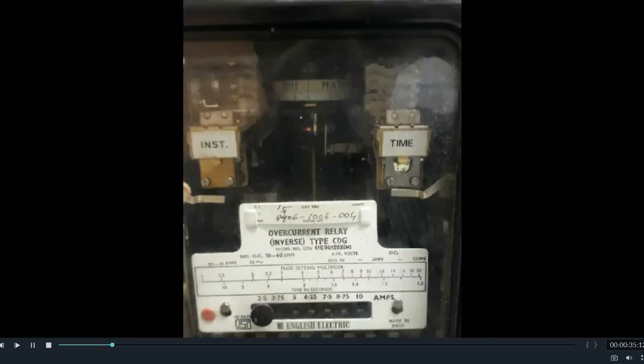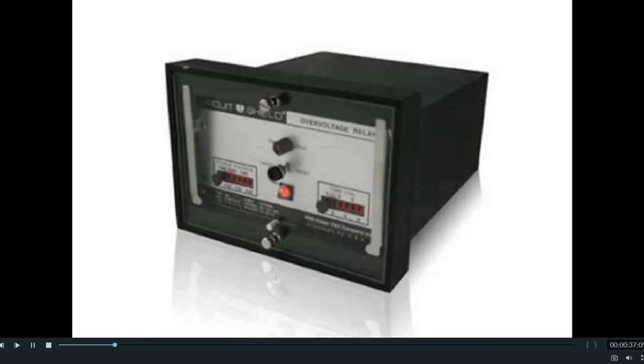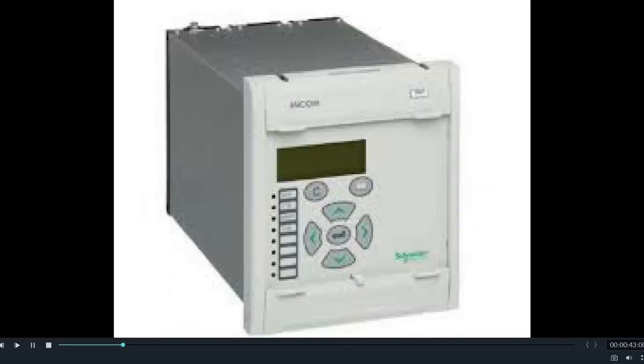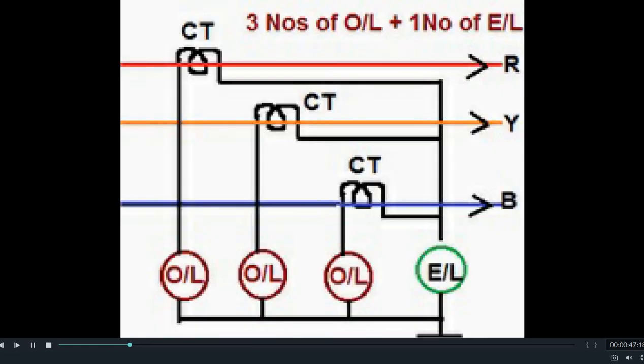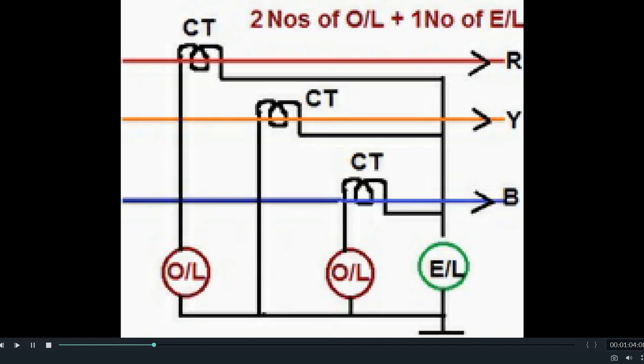These relays are available in all types — electromechanical, static relays, and numerical relays. Overcurrent and earth fault relays are generally used in groups. For any transmission line, there are always three overcurrent relays for three phases and one earth fault relay connected in the neutral of the CT secondary circuit. But in many cases we observe that there are only two overcurrent relays and one earth fault relay used in combination for the protection of any feeder.